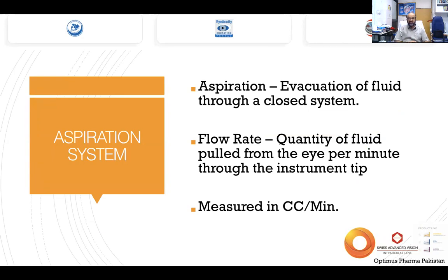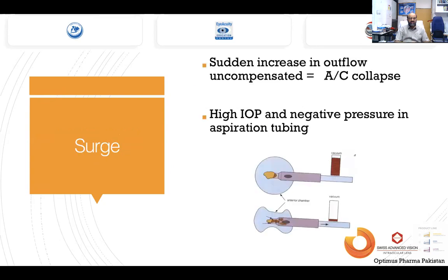Aspiration is evacuation of the fluid through a closed system. The quantity of fluid pulled out of the eye per minute is known as AFR, aspiration flow rate. It is in cc per minute, whereas the unit for the vacuum is millimeters of mercury. We have already discussed that the negative pressure induced in the aspiration tubing is the vacuum, or the holding power.